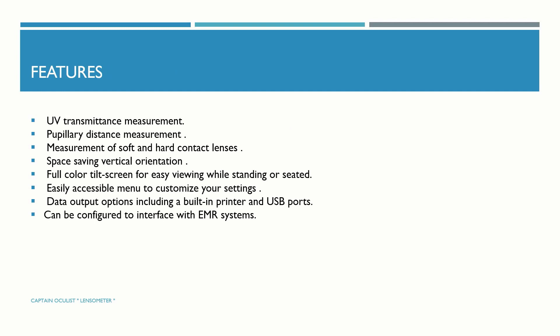Features of the automated lensometer include: UV transmittance measurement, pupillary distance measurement, measurement of soft and hard contact lenses, space saving vertical orientation, a full-color tilt screen for easy viewing while standing or seated, an easily accessible menu to customize settings, data output options including a built-in printer and USB port, and it can be configured to interface with an EMR system.